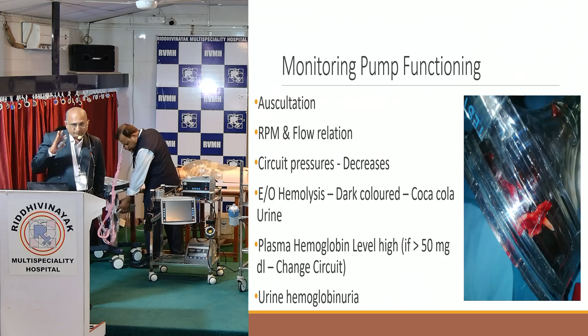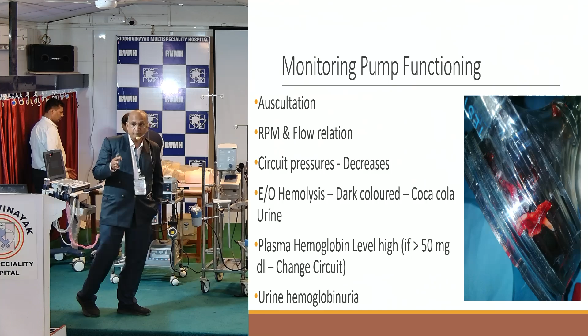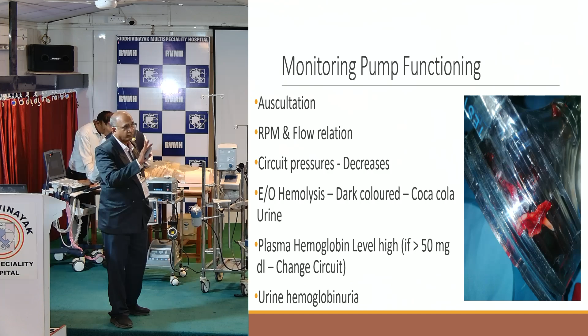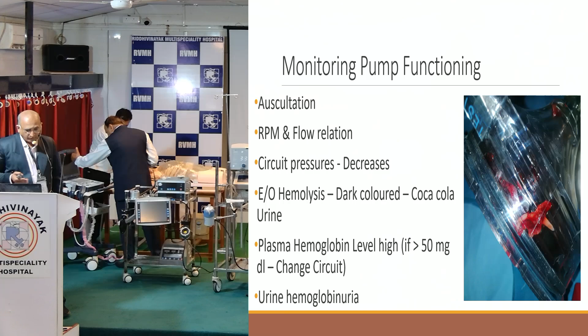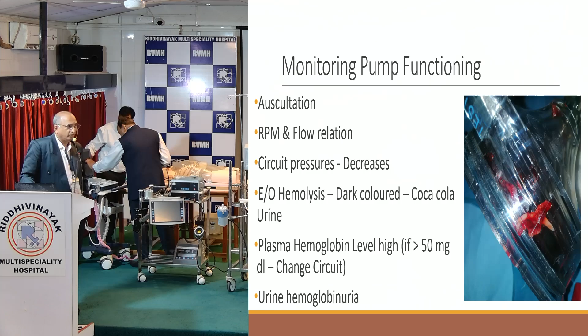You have to look at the RPM and flow ratio. With the same RPM the flow decreases, look at the circuit pressures. If all the circuit pressures are down and with the same RPM the flow is decreased, that goes in favor of something wrong with the pump. You might also see evidence of hemolysis: dark color urine, plasma hemoglobin level goes up, and you get urine hemoglobin. So these are all the ways you can monitor the pump function.